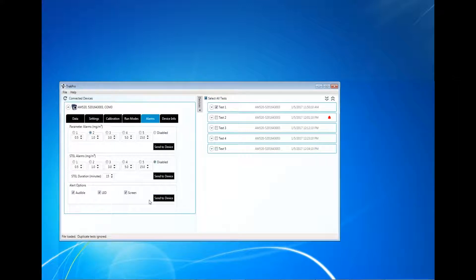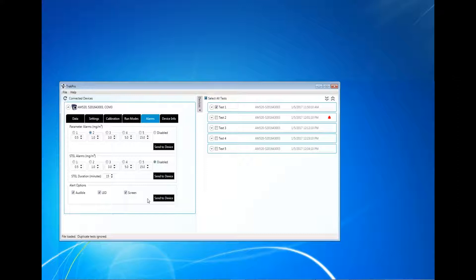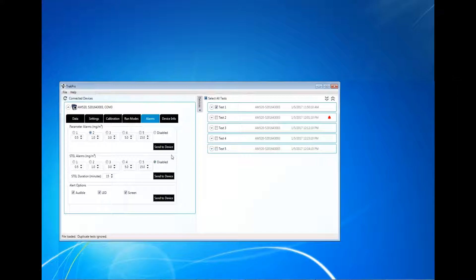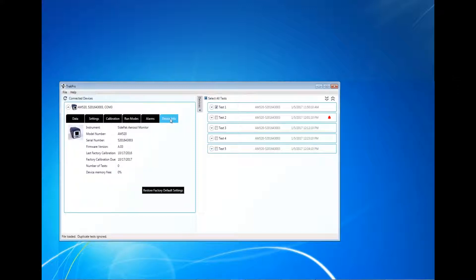LED refers to the four red LEDs that are on either side of the AM520 display. These four LEDs will illuminate when an alarm set point is triggered. Screen refers to the AM520 display itself. This will also change to red when an alarm set point is triggered.